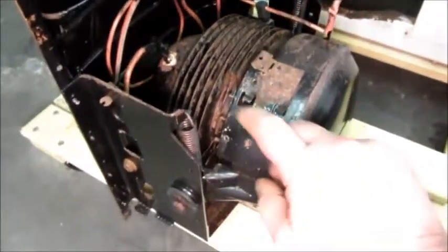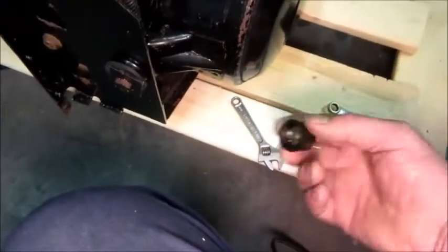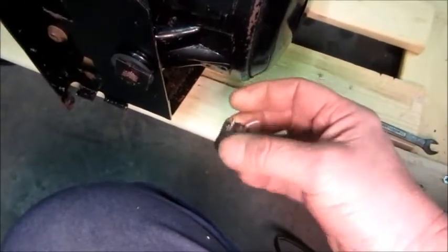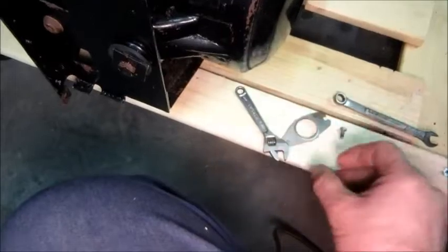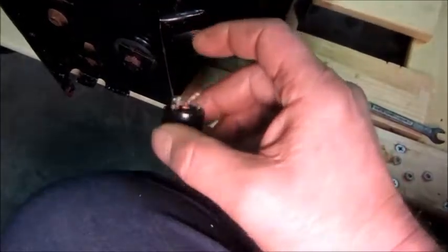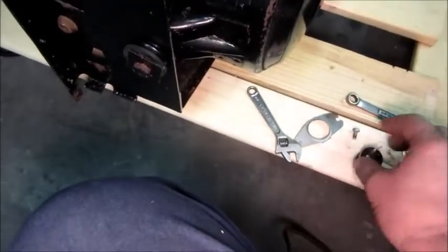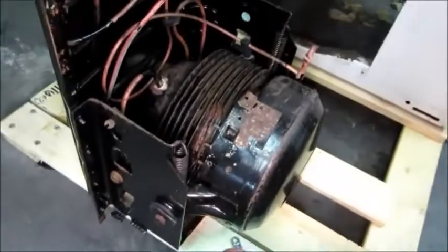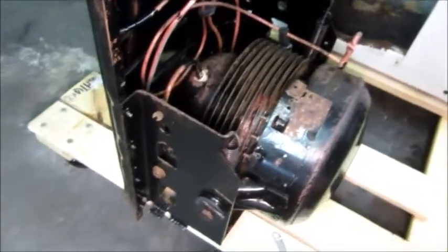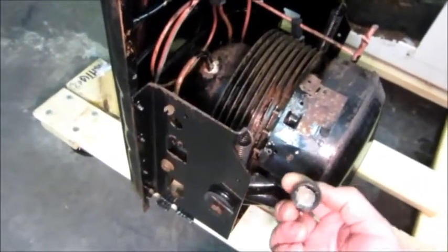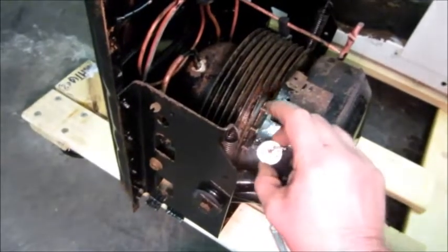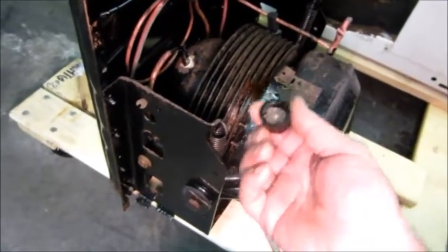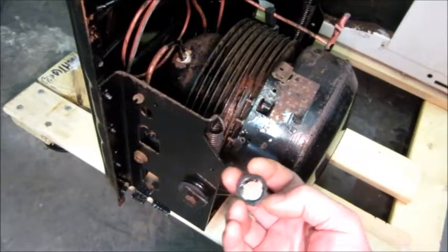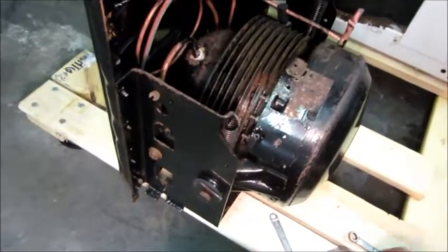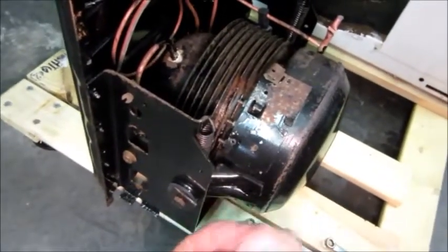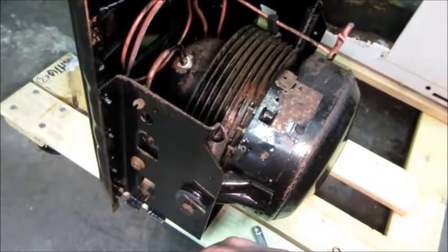And then put the new overload breaker on. That's the old one. I went ahead and got it wet washing it, so I knew it was bad anyway. It looks nice, but I wouldn't trust it. I think probably when the start relay stopped working, the compressor would try to start and it just tripped this overload over and over and over again because it couldn't start. And it might be badly worn in there, so again, I don't trust it. It's a cheap part, less than 20 bucks, so I'm going to put a fresh one on. Better to be safe than sorry.